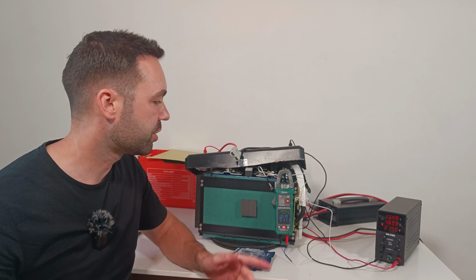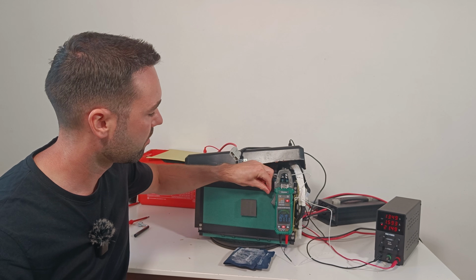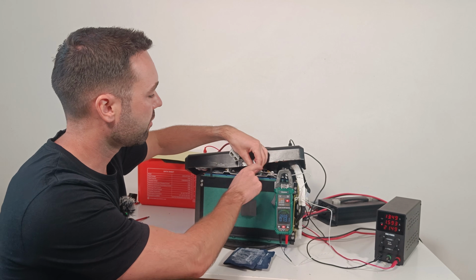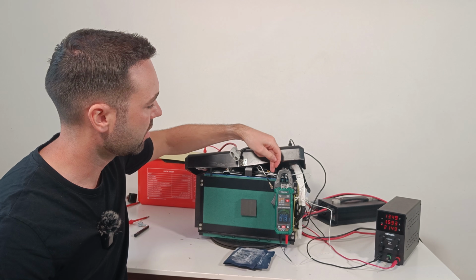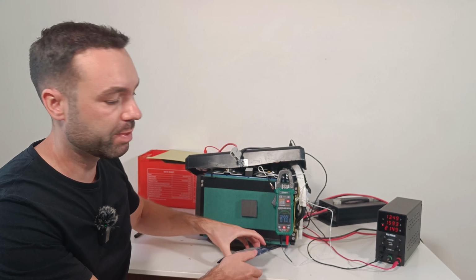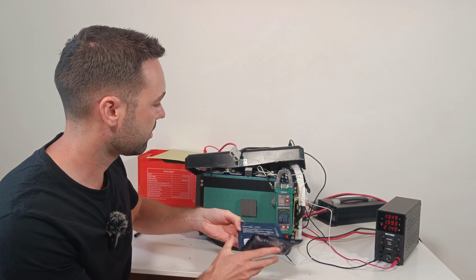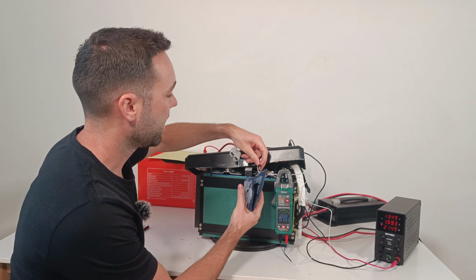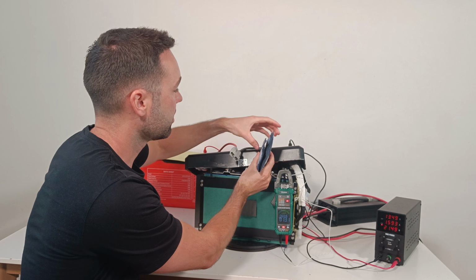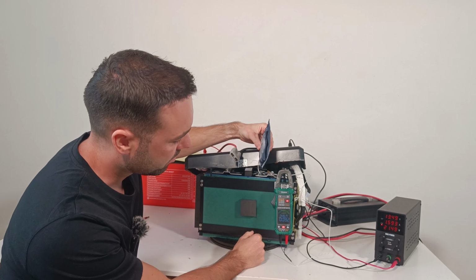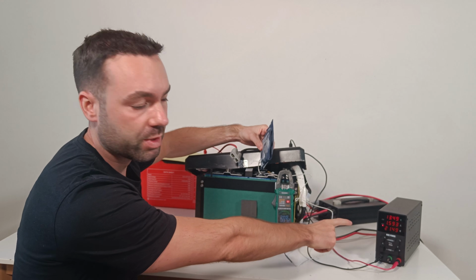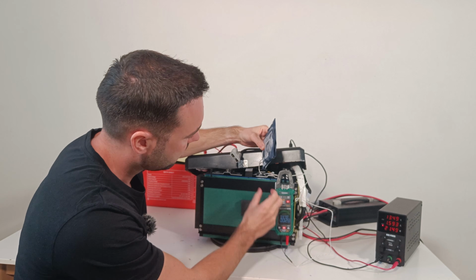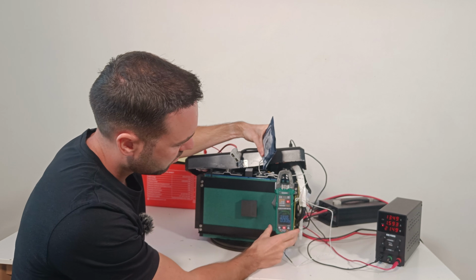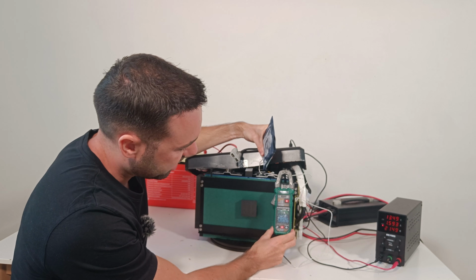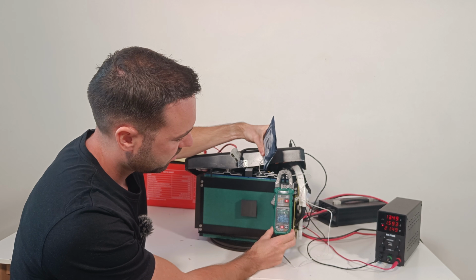Let's do the low temperature disconnect test. I've removed the lug from the balance lead position, and I will now apply a cold pack. I have added another thermocouple on the meter here. We are now charging with 1.5 amps, and we are at 0 degrees.